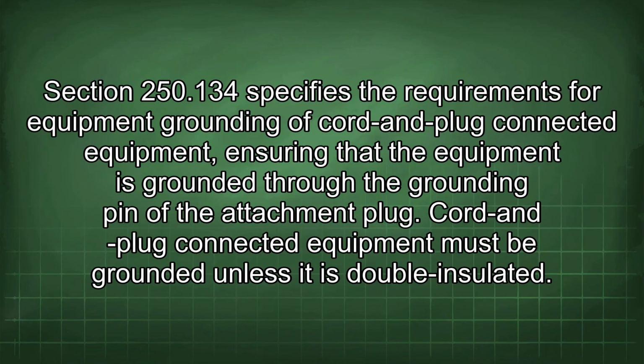Section 250.134 specifies the requirements for equipment grounding of cord and plug connected equipment, ensuring that the equipment is grounded through the grounding pin of the attachment plug. Cord and plug connected equipment must be grounded unless it is double insulated.